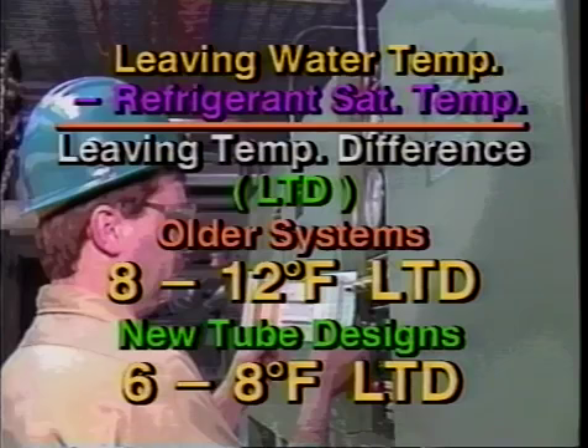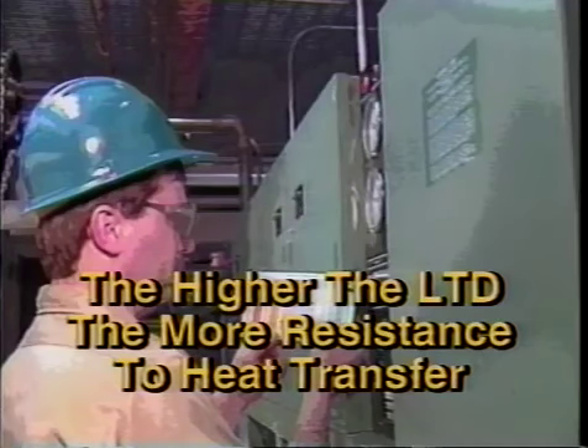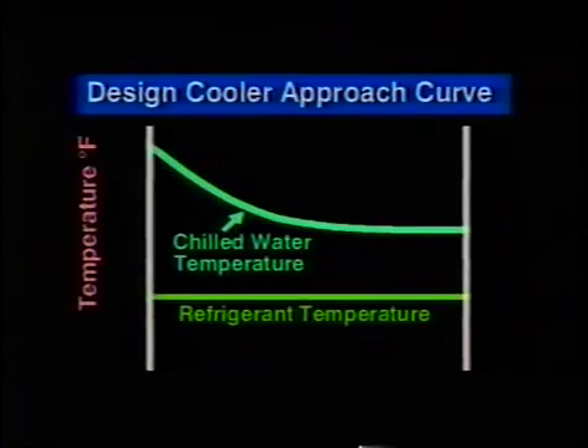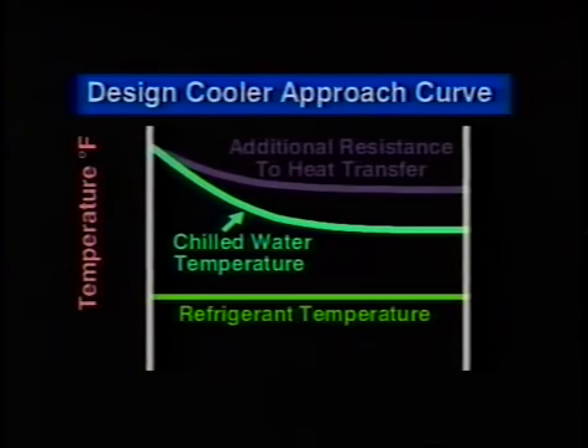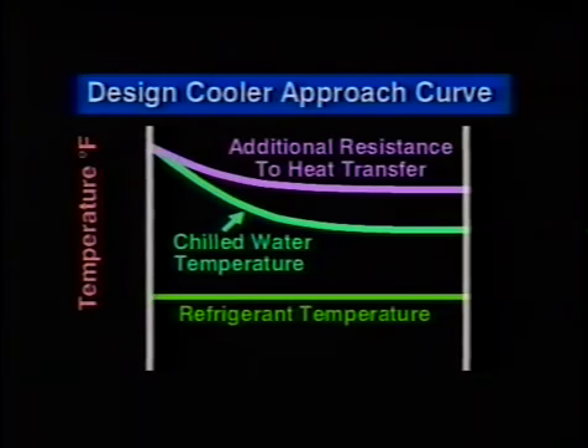The LTD gives an indication of resistance to heat transfer. The higher the LTD, the more resistance to heat transfer. It's helpful to visualize the water temperature versus saturated refrigerant temperature in what we call an approach curve. The approach curve provides a visual indication of the resistance to heat transfer between the water and the refrigerant. As the slope of the curve decreases, it indicates additional resistance to the heat transfer.